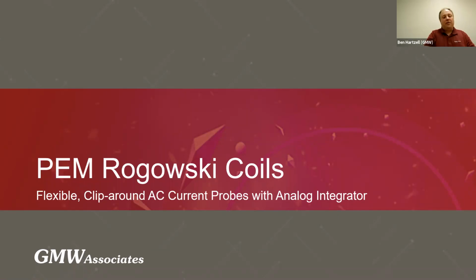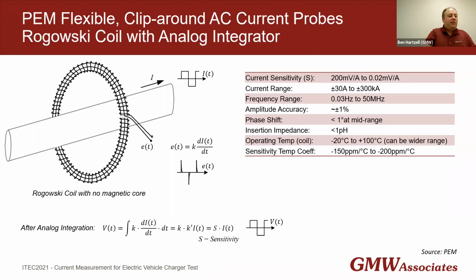The first type of current probe I'm going to talk about today are PEM Rogowski coils. PEM is the manufacturer, and these are flexible clip-around AC current probes with an analog integrator. A Rogowski coil is an evenly wound coil with a known number of turns and a constant cross-section. The end terminal is then passed back through the center of the coil so that both end terminals end up coming out on the outside of the same end of the coil. What this means is if you have a Rogowski coil made of flexible material, you can open and close it. You don't need any electrical join in the joint. It all passes back through the same coil.